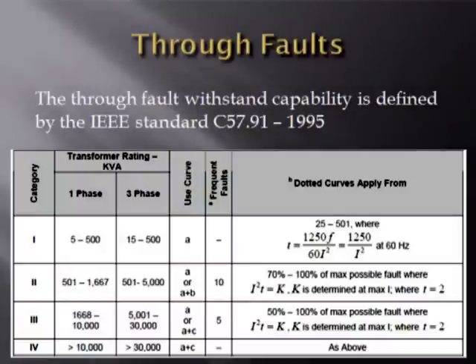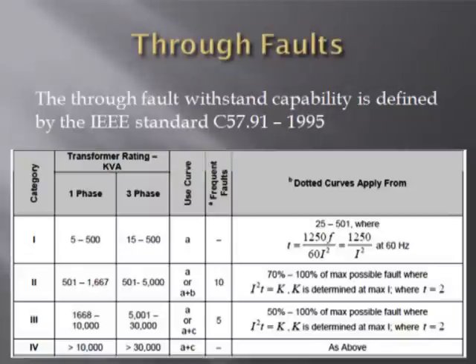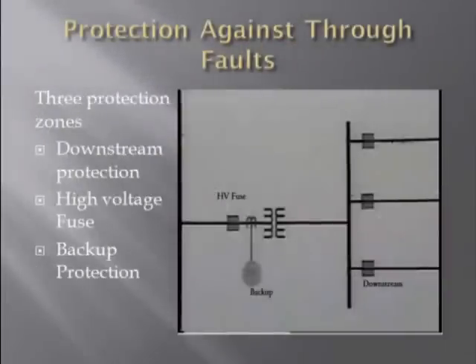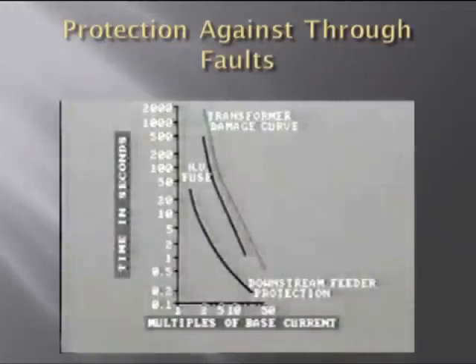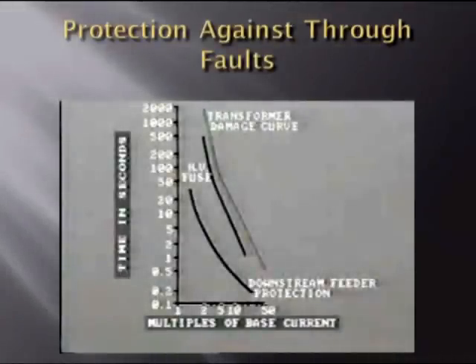Through-fault withstanding capability has been divided by the IEEE standard into four categories as indicated in the table. It is represented as a curve plotted between multiples of normal current and the allowable time. In this example, a transformer feeds three feeders through a bus bar. If a fault occurs in any of the feeders, the respective protective system of the feeder — called the downstream protection — operates. If it fails to operate, then the high voltage fuse on the primary end of the transformer works. As the HV fuse cannot sense small faults, a backup relay like a 51G relay must be employed. The graph shows that downstream protection operates before the fuse, and if both fail, the system may be damaged.